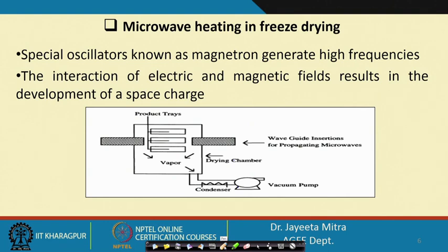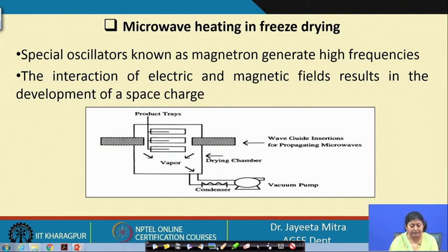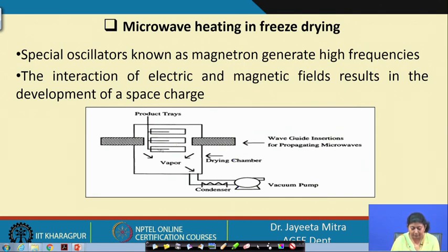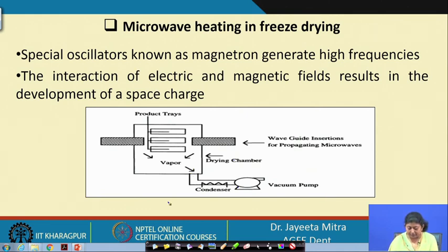Next is microwave heating in freeze drying. Microwave heating is a volumetric heating, so heat generation is very fast. Special oscillators known as magnetrons generate high-frequency electromagnetic radiation, and the interaction of electric and magnetic fields results in the development of space charges. Products are kept on trays, volumetric heat generation occurs on the product trays, vapor comes out going to the condenser where it forms ice crystals, and the vacuum pump continuously maintains the reduced pressure level in the chamber.